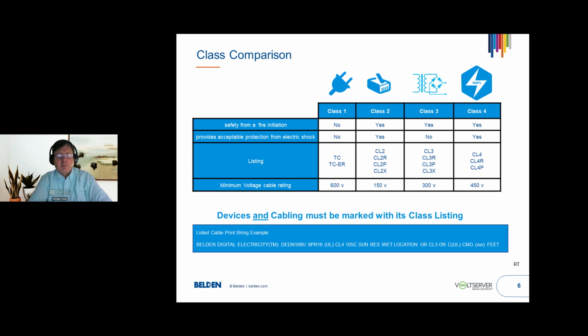The important thing to remember, though, is that the voltage rating on these cables is not written on the cable, and that's done for a purpose. The reason Class 2, 3, and 4 cables do not have the voltage rating on them is that we don't want somebody who doesn't understand that it's a Class 2 or 4 cable to pick it up, see that it's 150 volt, 300 volt, 450 volt, and say, "Oh, I'm going to wire my lamp with that." We don't want that to happen. So on purpose, within the NEC and UL, we do not add that to the cabling.